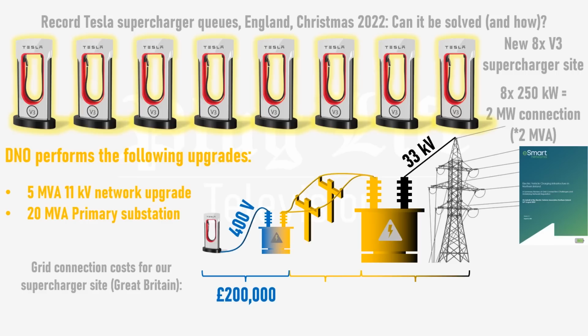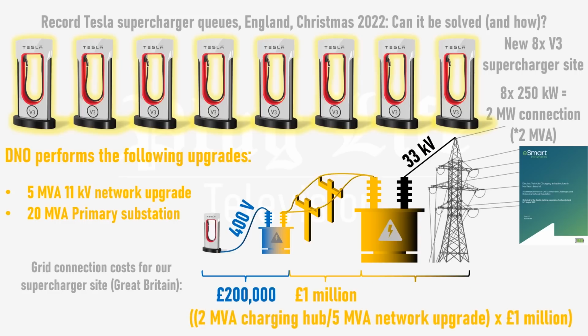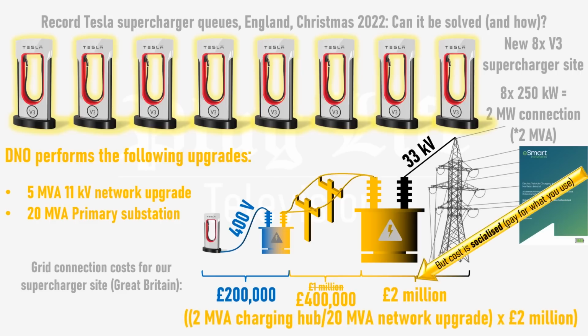The 11 kilovolt network upgrade would cost £1 million, but in Great Britain, this cost is socialised, so each customer only pays for the amount of capacity that they use. In this case, we require 2 out of the 5 MVA available, which works out at £400,000. The new primary substation is £2 million, but again, this cost is socialised, so we pay £200,000.